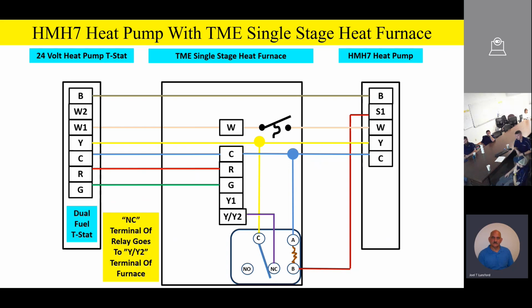Now the normally closed contact on the relay will go to Y/Y2. That's our high-speed airflow input on the furnace control that commands high-speed airflow. And again, we're going to set that up for 100% airflow. We want to make sure we adjust our airflow for 100% airflow on a Y/Y2 call. And then the normally open contact will go to Y1, our first stage of cooling airflow. So this is our block diagram for the TME single stage heating, two-stage cool furnace. An example would be like a TM8E or a TM9E furnace. This is how you're going to wire the thing.